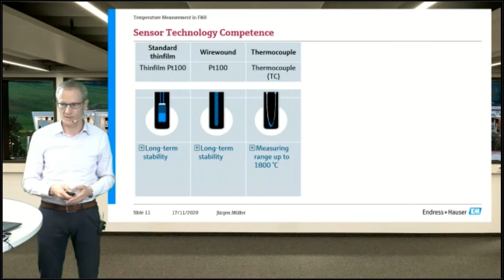But Endress+Hauser wanted to offer something special, so we developed some very special sensors. First, there is the Strong Sens, which we offer for applications with very strong vibrations. It's a PT100, but the sensor offering the best vibration resistance available - you can use it up to 60 G, while normal PT100 sensors are normally just used up to 3 G.